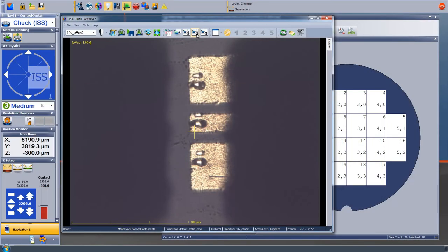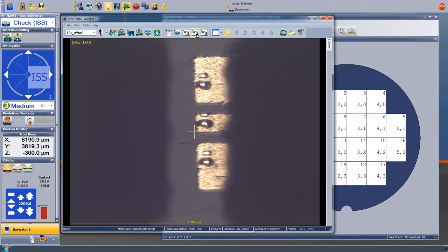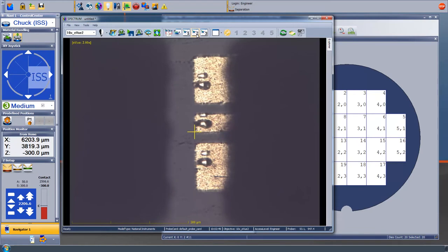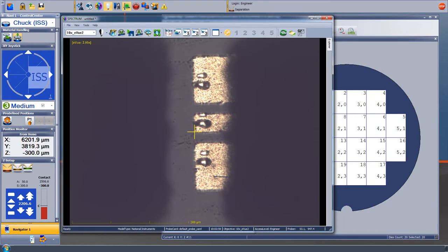In order to do automatic probing of the calibration structures, we will need to do a manual alignment of the ISS substrate with respect to the probes. We align the crosshairs to the lower left corner of a structure that will repeat across the substrate. In this case, it's the signal trace of a through connection.